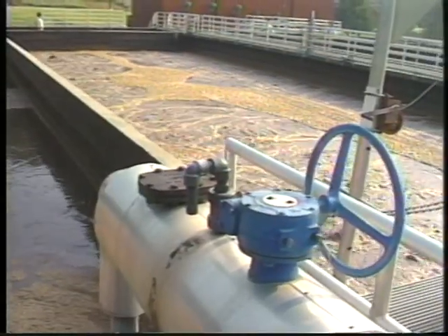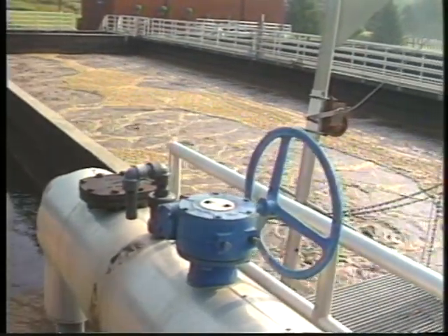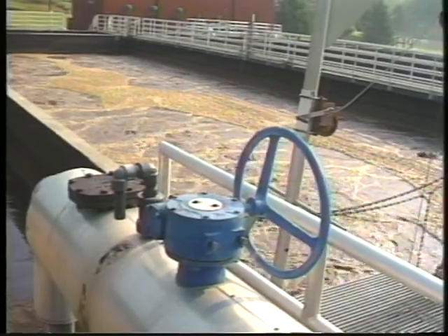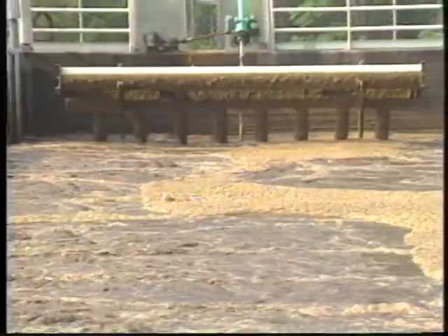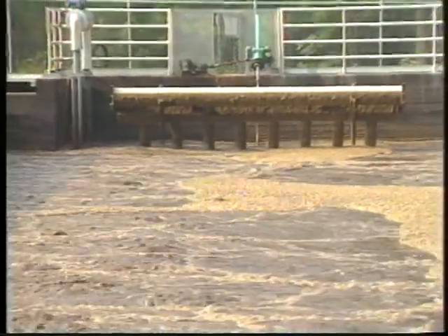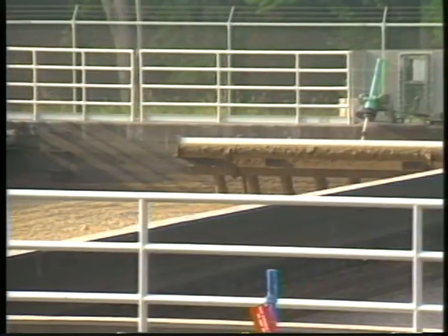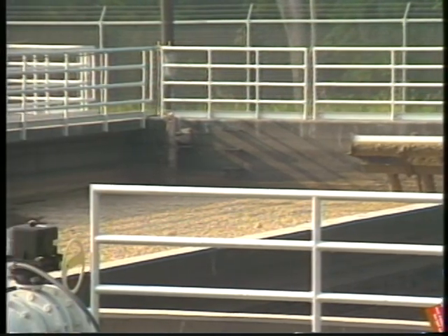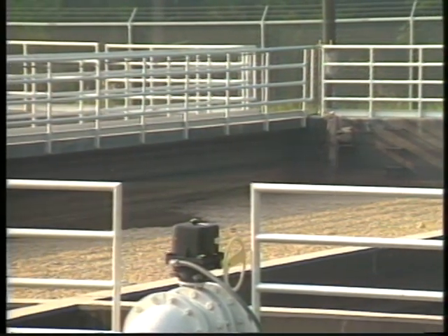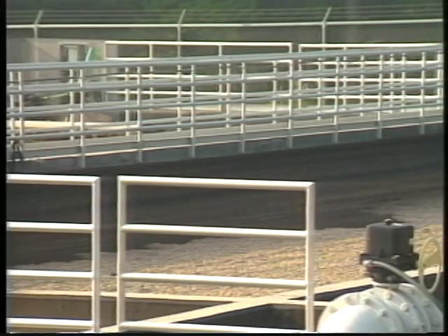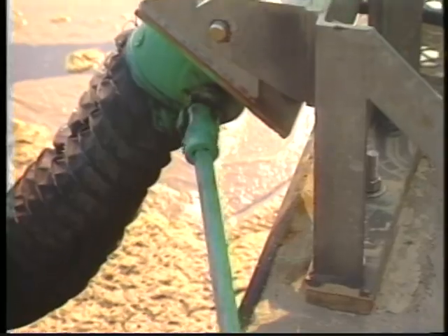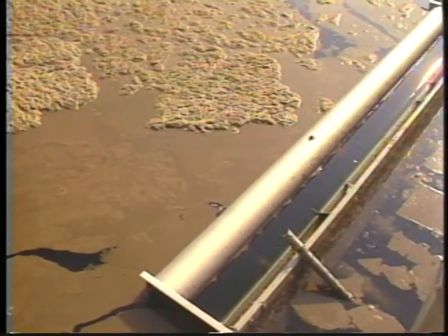In this mode, the contents of the tank may be mixed and aerated as well. The mixing and aeration mode, when the tank is full and the microorganisms feed on the pollutants in the water. In this mode, no wastewater is entering or exiting the aeration tank. The settling mode, where the tank essentially becomes a clarifier. No mixing, aeration, or filling takes place. The decanting mode, where some type of decanting device lowers into the tank and removes the treated wastewater from the aeration tank. Usually sludge is wasted from the tank in this mode as well.